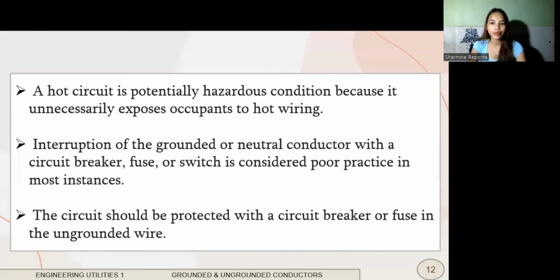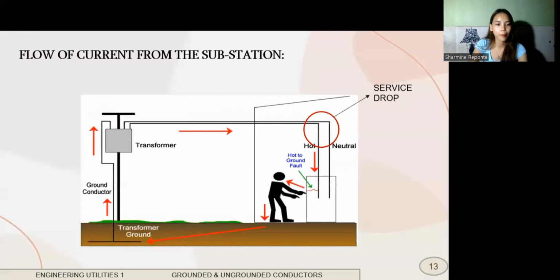The circuit should be protected with a circuit breaker or fuse in the ungrounded wire. All wiring system or circuit should be protected by circuit breaker. A circuit breaker is an electric switch designed to protect an electric circuit from damage caused by overcurrent, overload, or short circuit.